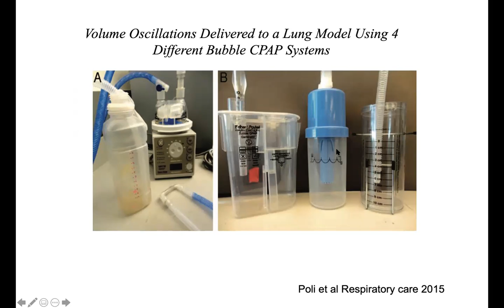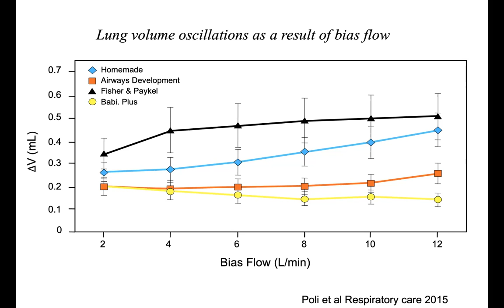This is looking at those small tidal volumes that CPAP is providing, and it's comparing the Fisher-Paykel device, which is shown at the top over here, the homemade device, which is the blue diamonds or turquoise diamonds, and then the two others, Babi Plus and Airways Development. And you can see here that the oscillations or the small tidal volume being produced is highest actually in the Fisher-Paykel device than it is in the homemade device, but it's similar as you get up to higher flow rates, but much higher than the other two bubble CPAP systems. Now, the thing you need to remember about the other bubble CPAP systems is they have a diffuser at the end of the expiratory limb, and that diffuser prevents those oscillations or bubbles from providing a small tidal volume.